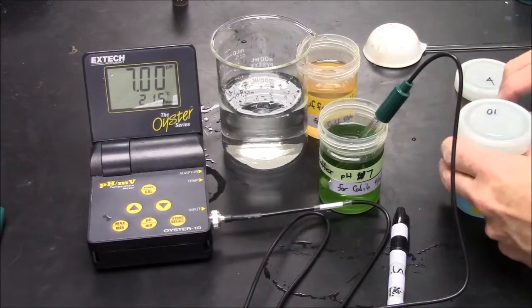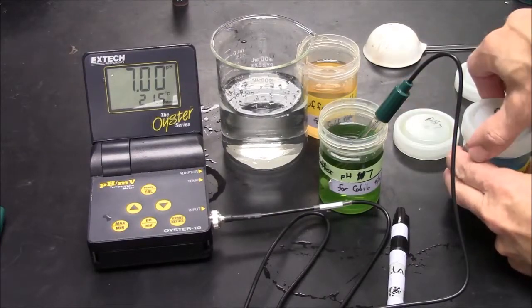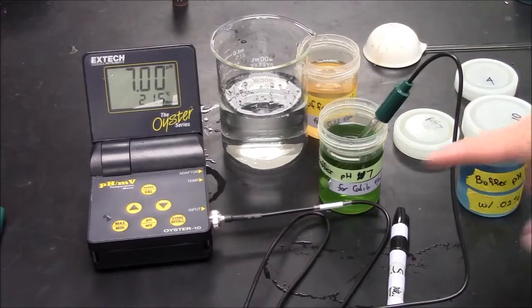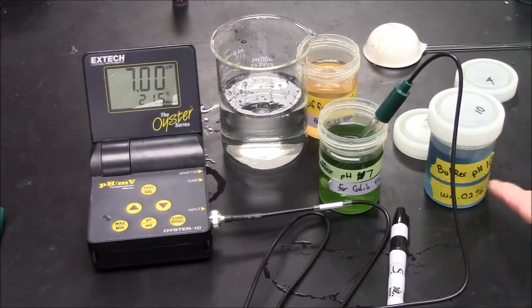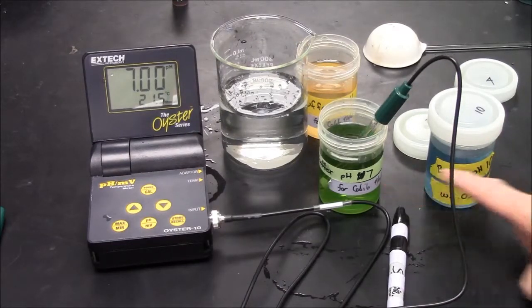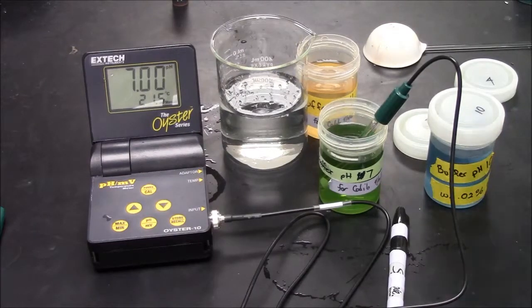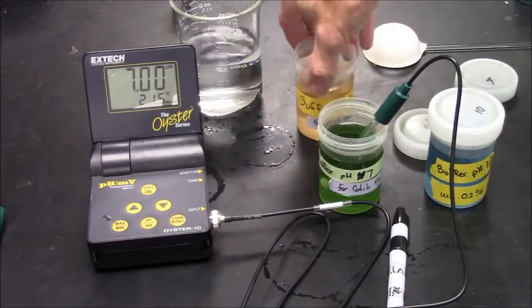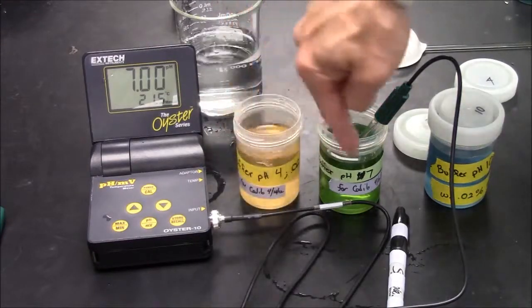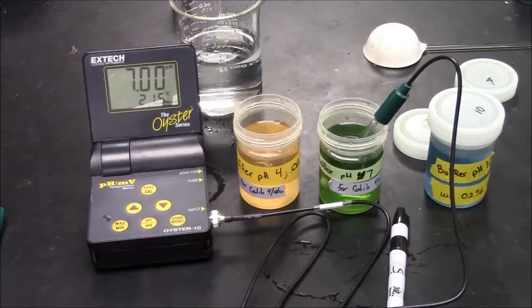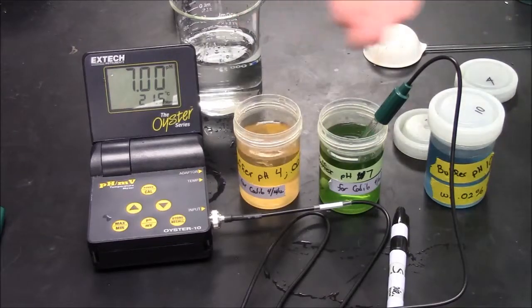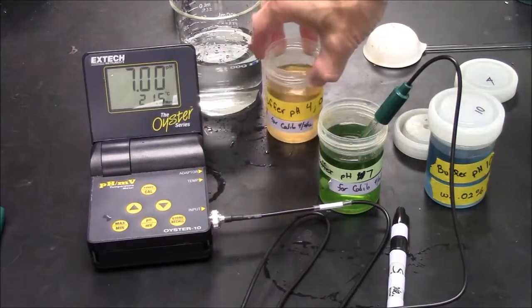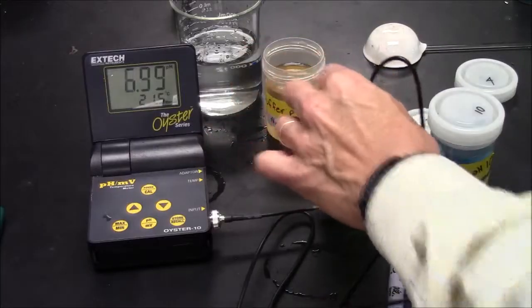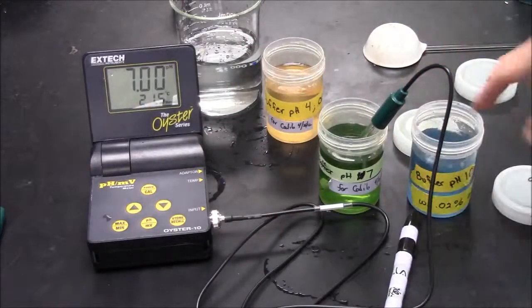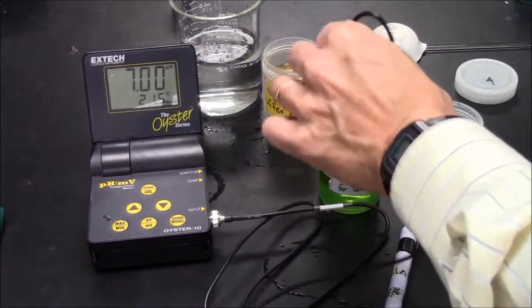To get the pH meter to work within a range of pH values, I need a second point. If the buffer that I'm trying to measure will have a high pH, then I will use pH 7 and 10 as my standards for the calibration. If my buffer has a low pH, I will use 4 and 7 as the 2 points for the calibration. It's very unlikely that all 3 points will line up for you on the pH meter. In this case, I will use the pH 10 buffer to calibrate the second point.